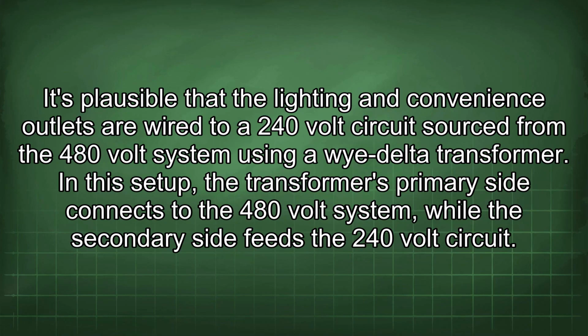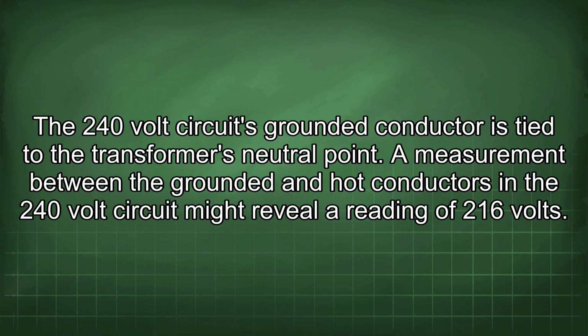It's plausible that the lighting and convenience outlets are wired to a 240-volt circuit sourced from the 480-volt system using a wye-delta transformer. In this setup, the transformer's primary side connects to the 480-volt system while the secondary side feeds the 240-volt circuit. The 240-volt circuit's grounded conductor is tied to the transformer's neutral point. A measurement between the grounded and hot conductors in the 240-volt circuit might reveal a reading of 216 volts.